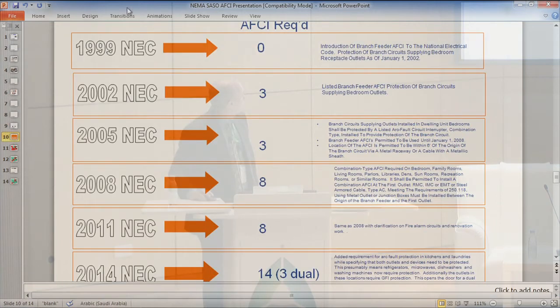When we went through this, initially in 1999, there was no requirement for arc fault circuit breakers. In 2002, it averaged 3 per home, and these were basically used in circuits around the bedrooms because we felt like that was a great place to start. There was not a whole lot of vacuum cleaners and so forth being attached in those areas that would have been difficult to, or could have caused nuisance tripping.